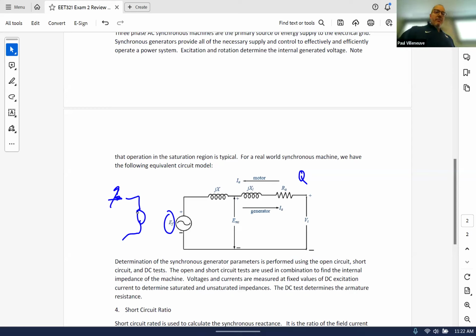And that means that the magnitude of Q, or EF, I'm sorry, is going to increase or decrease, which means you have magnetic field supplied internally or externally. The inductors don't care. The inductors just need magnetic energy. So they'll either take it from the internal system because you have sufficient excitation, or they'll just steal it from the grid. They're perfectly happy to get it either way. And that's why you can have leading or lagging power factor in a real world synchronous generator.